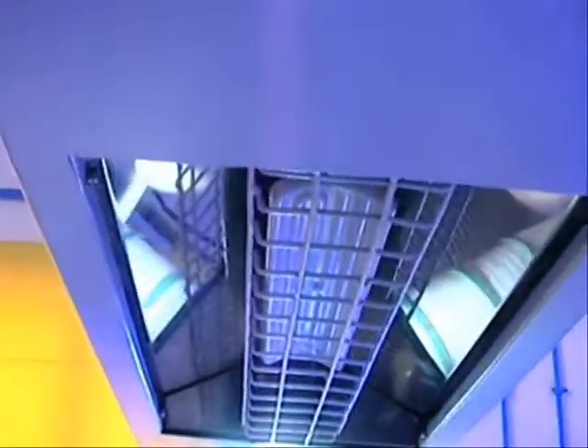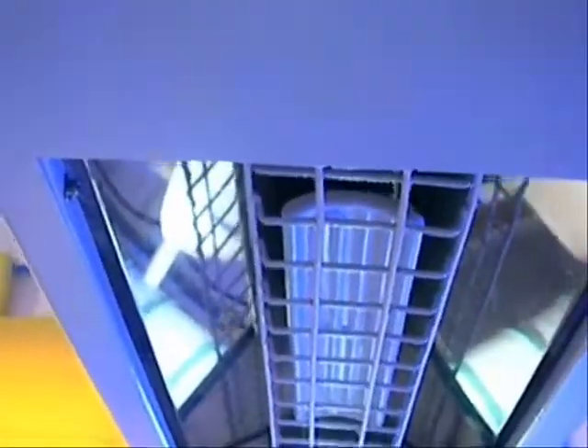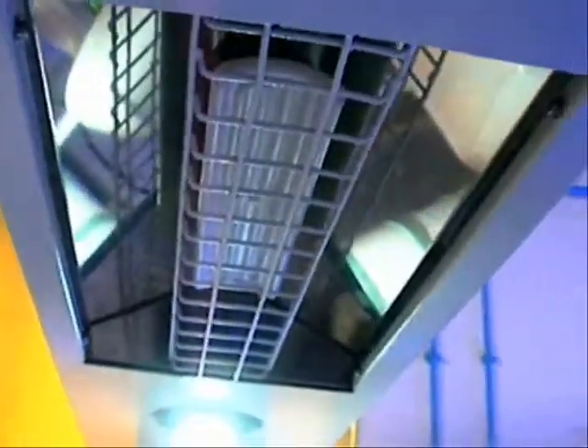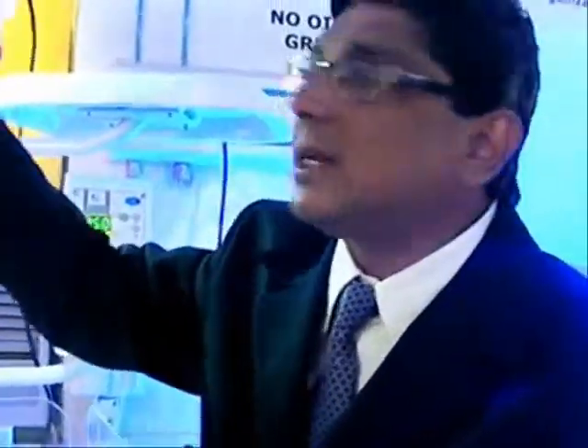Plus, if you go to the smaller features like the heating device, we have not used a traditional heating coil system. In the traditional heating coil system, after a certain period of time, due to humidity, it gets oxidized and the coil breaks, so you need to service the warmer. Here we have used a concealed ceramic heater, which is again a CE certified component. So it's much more effective as compared to the conventional infrared quartz heater. The energy efficiency transmission is 96% as compared to 60% of an infrared quartz heater.